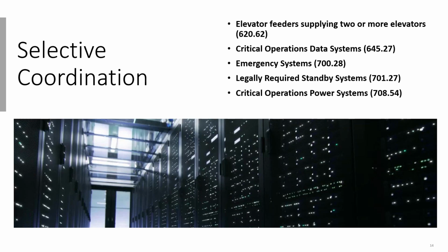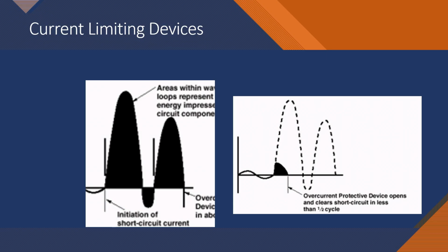Okay, selective coordination, feeders supplying 2 or more elevators, critical operation data centers, emergency systems, legally required standby systems, and critical operation power systems, or COPS. Okay, and that's pretty much that. So while we're talking about this, there are such things as current limiting devices. Something that I've noticed, there seems to be a lot of confusion, even on the part of many engineers, of what can and can't happen with current limiting devices.